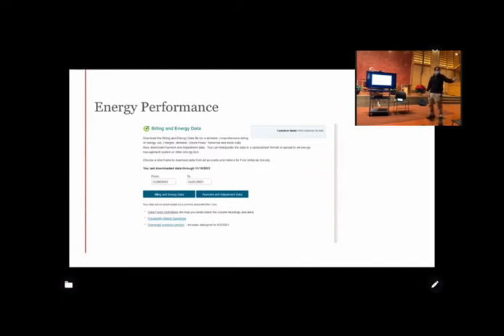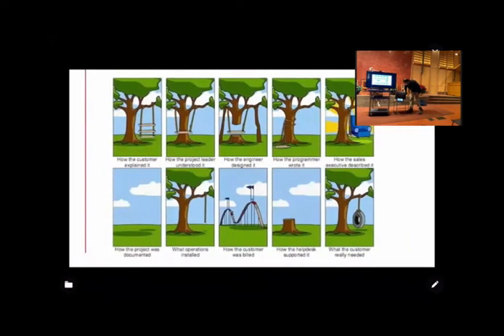So Tom has the data, and I don't know. We think the building, between the solar and the recommissioning stuff, has halved the energy usage. Is that right, Mark? So we've saved 25% on our electric bills, right? Pretty much. That's from turning off the controlling the 15 horse motor. We think that was costing us $800 a month, 24/7. At high pressure, it was way up the pump curve.